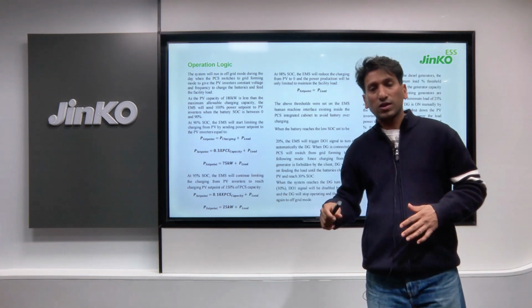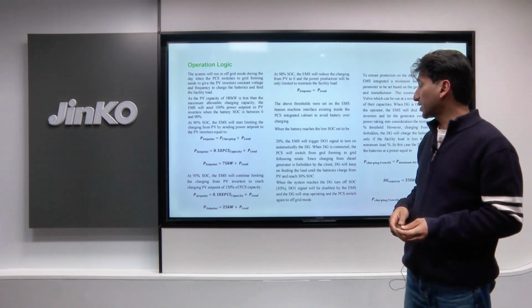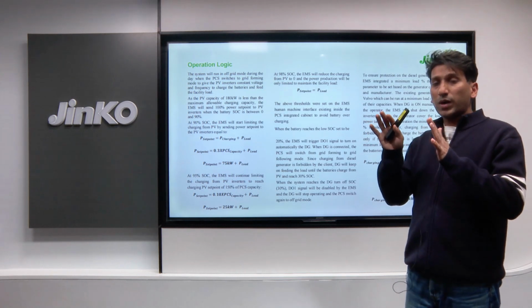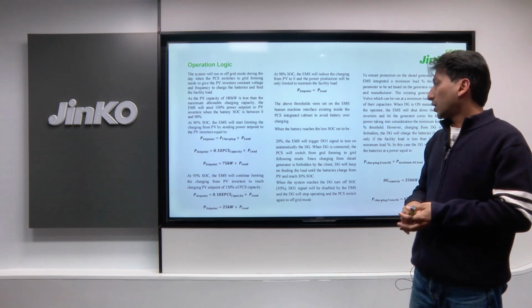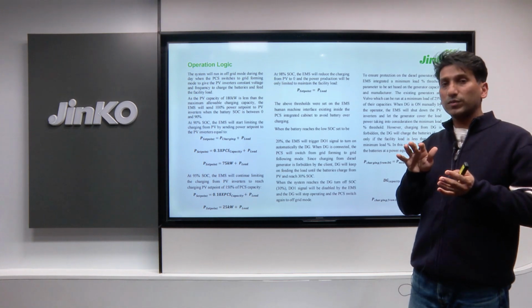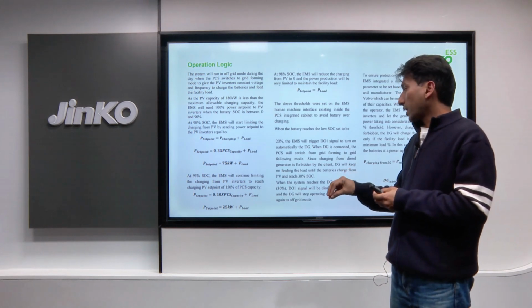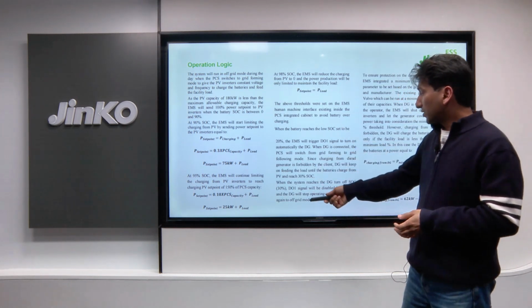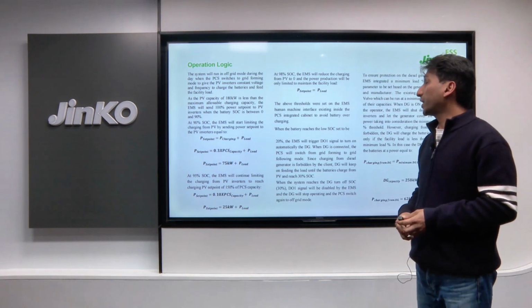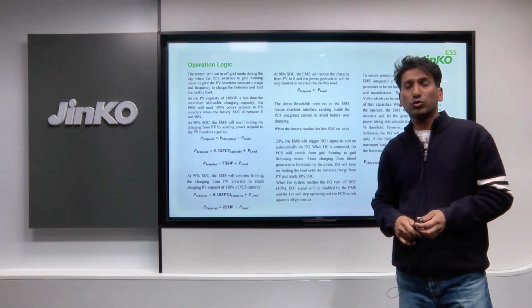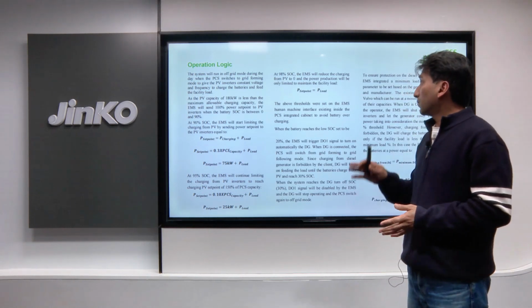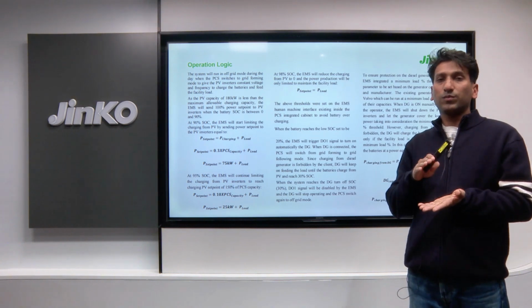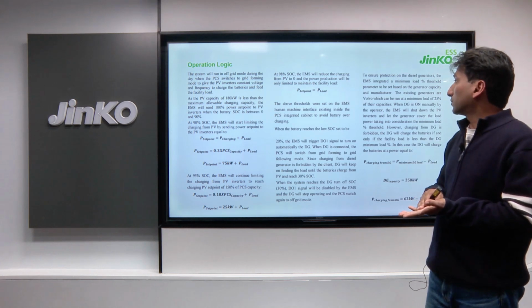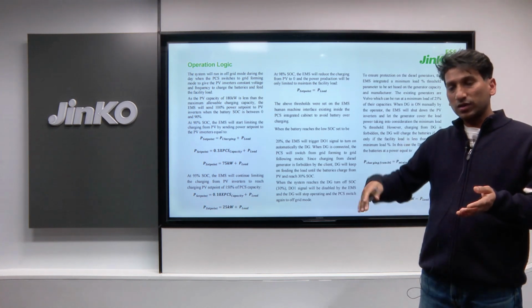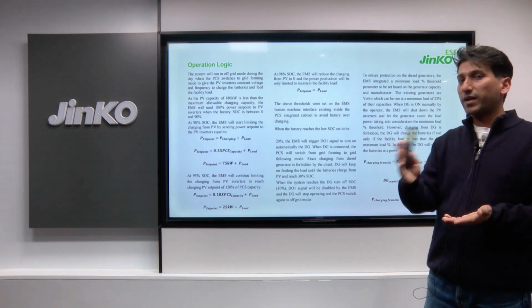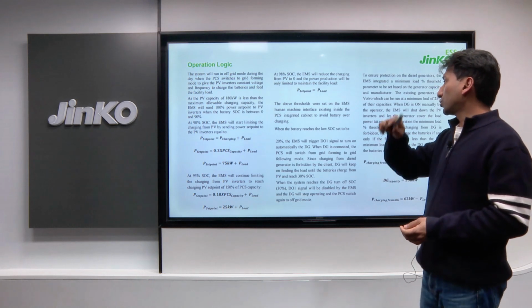But when the SOC reaches 95%, the EMS will limit the power from the PV to 10%. So only 10% of the power from the PV inverter will be used to charge the batteries, and the rest is supplied to the load, as you can see in this formula. And when the SOC reaches 98%, in order for the batteries not to be overcharged, we limit the charging power from the PV to 0. After 98% SOC, all the power from the PV inverter goes directly to the load. It doesn't charge the battery at any time. So this is how the whole operation logic of the system works.